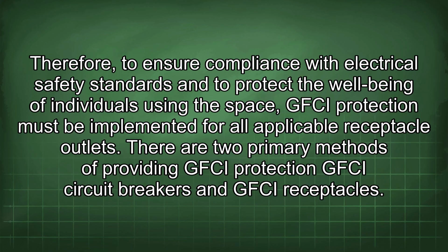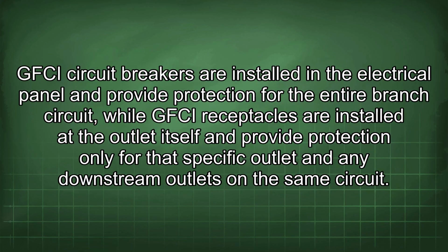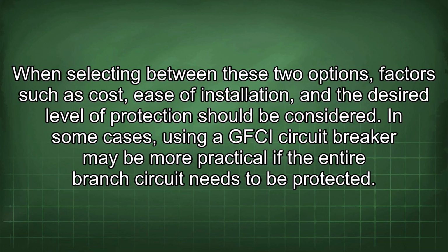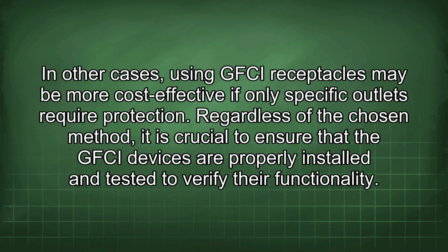There are two primary methods of providing GFCI protection: GFCI circuit breakers and GFCI receptacles. GFCI circuit breakers are installed in the electrical panel and provide protection for the entire branch circuit, while GFCI receptacles are installed at the outlet itself and provide protection only for the specific outlet and any downstream outlets on the same circuit. When selecting between these two options, factors such as cost, ease of installation, and the desired level of protection should be considered. In some cases, using a GFCI circuit breaker may be more practical if the entire branch circuit needs to be protected. In other cases, using GFCI receptacles may be more cost-effective if only specific outlets require protection.